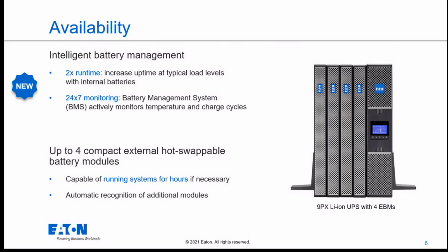And we have more accurate monitoring of the batteries, because in each lithium-ion battery there is a BMS, a battery management system, that reports or gives notification to the UPS on temperature of the battery, charge cycles, and many other parameters that we don't usually have access to with VRLA batteries. So this gives a more accurate view of what's happening on the battery side.